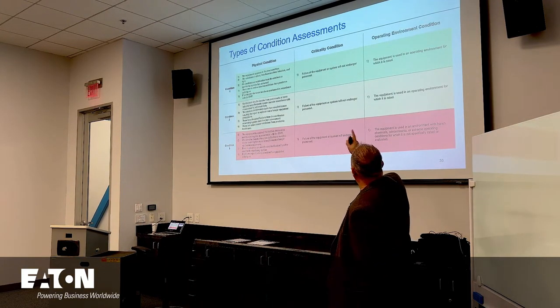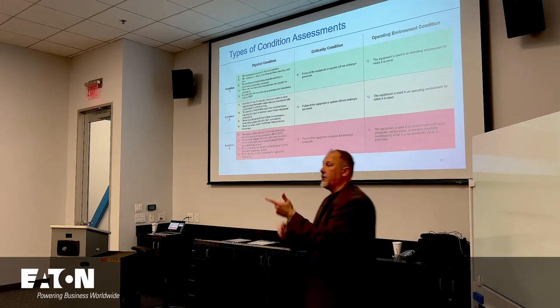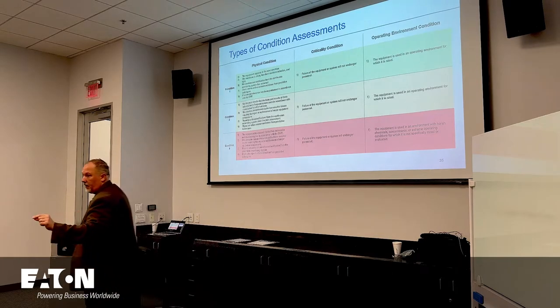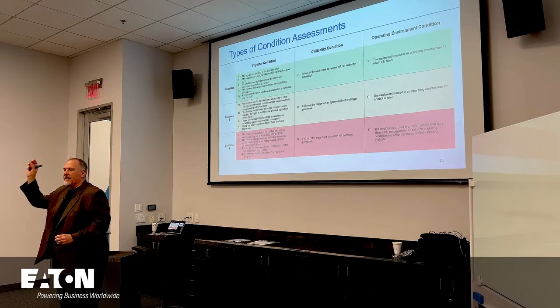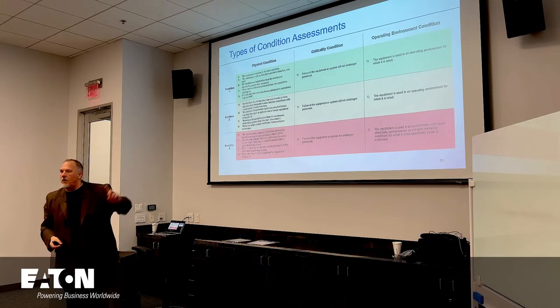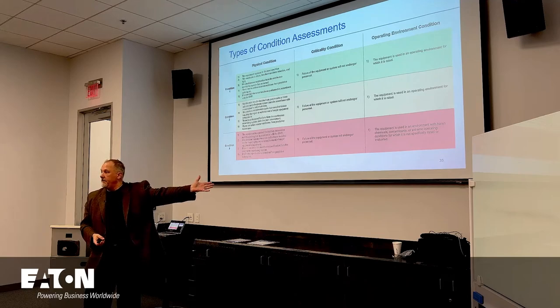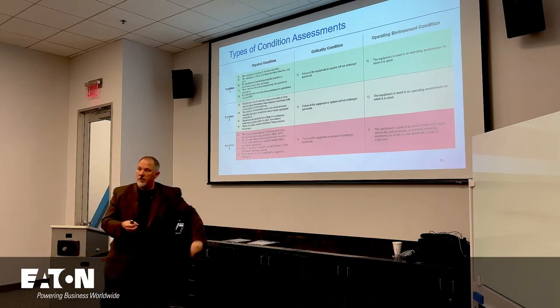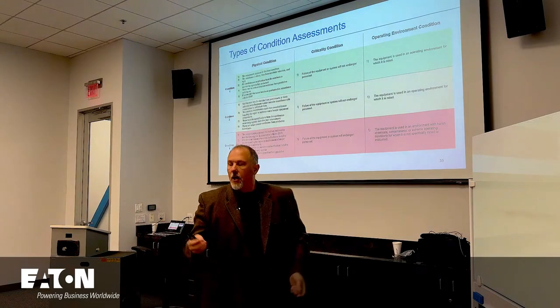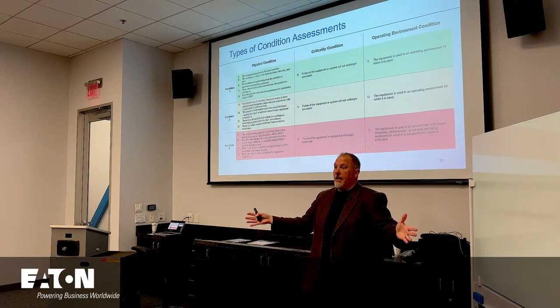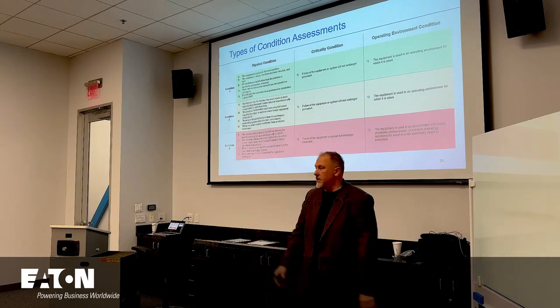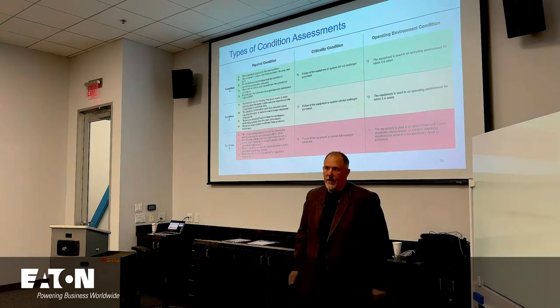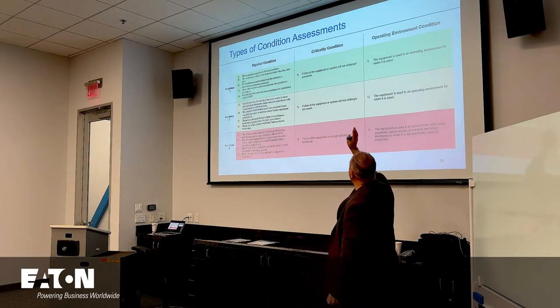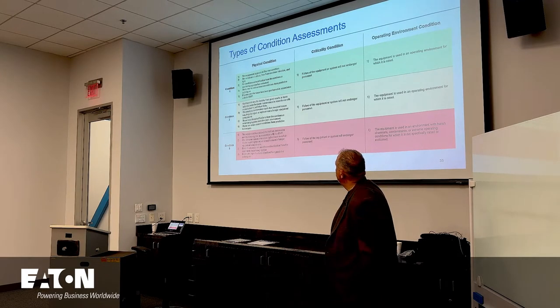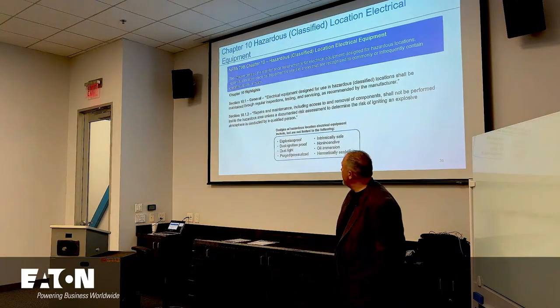So physical condition, critical condition, and operating environment. You've got to consider where your equipment is located. Do you think you have to perform maintenance on a circuit breaker that's in a marina right next to the water more often than one in your basement in a nice air-conditioned area? Probably. And do you think you might want to maintain an overcurrent device or piece of equipment more frequently when it's on your main production line, where if it goes down you're losing hundreds of thousands of dollars a minute? You might want to make sure that's maintained. So you've got to think about the physical condition, the criticality, and the operating environment - these are all the condition assessments.